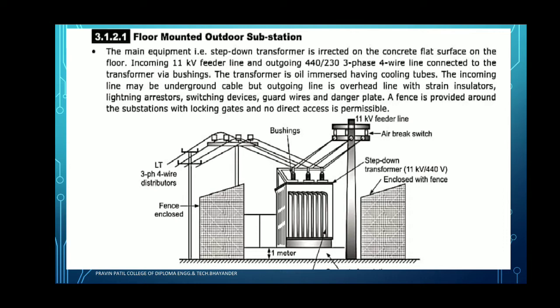Today we have to study floor mounted outdoor substation. This is the diagram representation for floor mounted outdoor substation. Here the 11 kV feeder line is the incoming. This 11 kV line directly feeds the step down transformer. That step down transformer converts 11 kV into 440 volt or 230 volt. That stepped down voltage, 230 or 440 volt with 3-phase 4-wire line, is directly connected to the consumer with the help of the floor mounted outdoor substation.